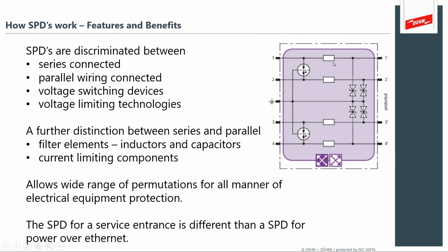And this schematic here to the right shows us a nice illustration. You have a combination of what are described as spark gap devices with a series fusing element with a high performance silicon avalanche diode on the protected side. So in this case, you might apply a series protection for a high-speed data network. In this case, what might be described as a 4-wire, for instance, RS-422 circuit coming from a security gate controller outside of your structure. And this allows for the protected side to be closest to your I/O control panel and your fire and safety alarm circuits. And here you see that combination of series and parallel devices with series and parallel elements to give you the fine-tuned connection that you're looking for.